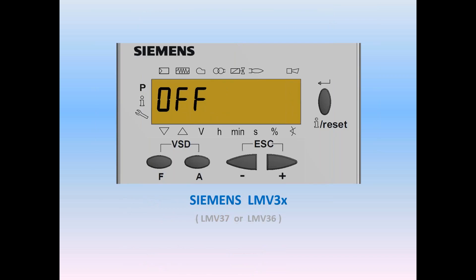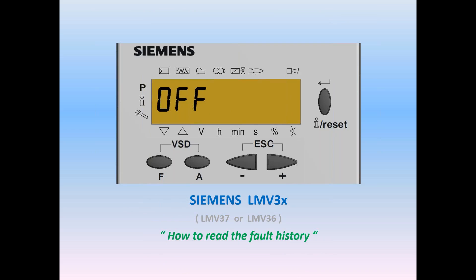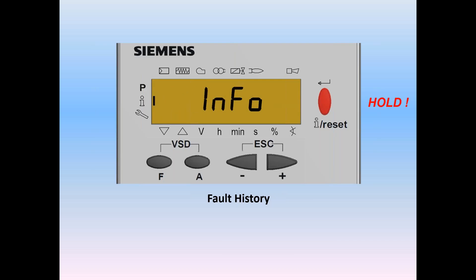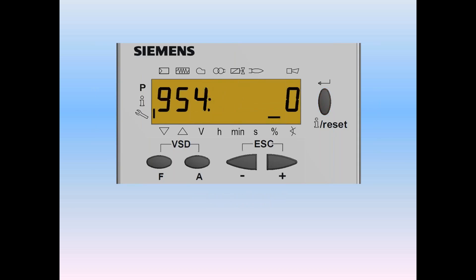Let's take a look at how to read fault codes on the Siemens LMV3, specifically the 3637. No login is required. Start by holding the reset button — don't let it go. The screen will say 'info'; keep holding it, and then it will say 'service.' Once it says service, you can let go.